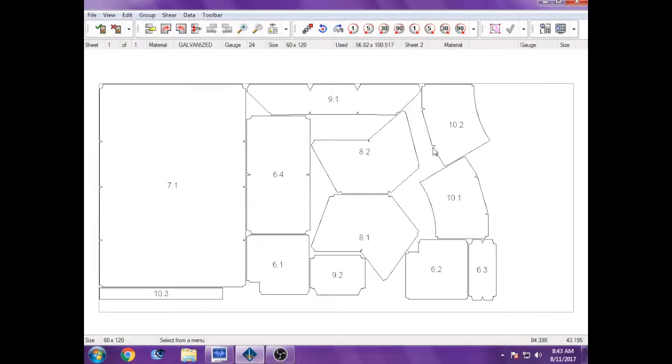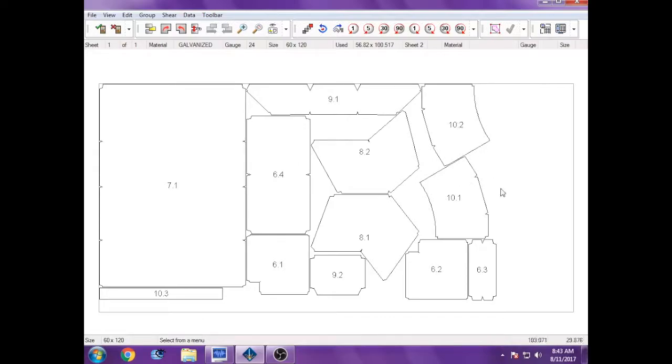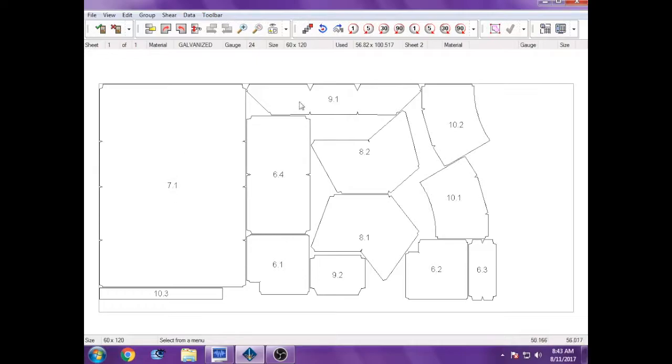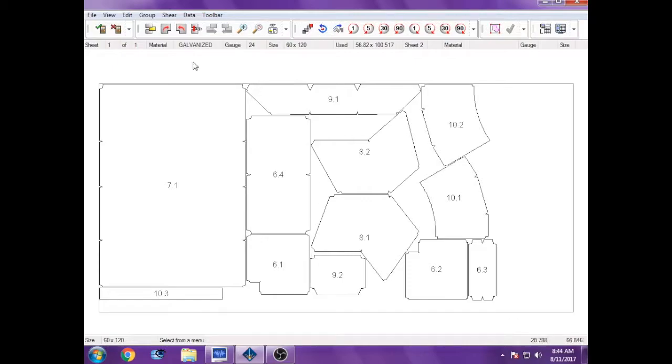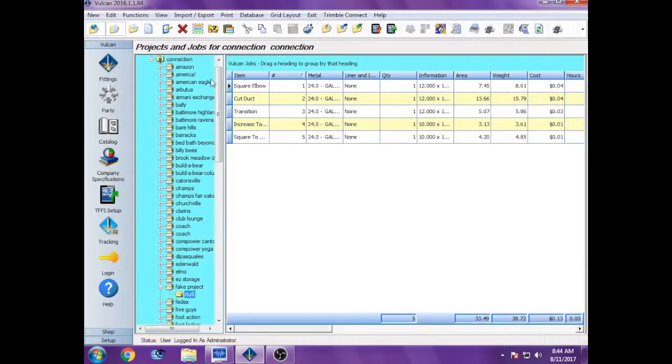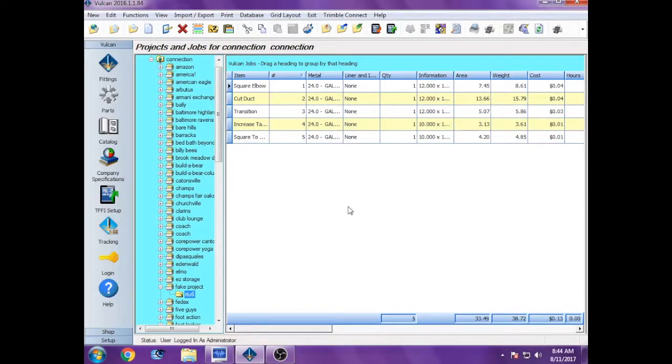So the elbow has two cheeks, a spine and a throat. Square to round, here it's in two pieces just like we asked it to be with a collar. This is the cut piece of duct. It's four, it's the three notches, so you know it's four-sided wraparound. And then the tap here, that's a tap edge increasing for a takeoff. And then there's the fourth side. This looks good, so it's save and exit.